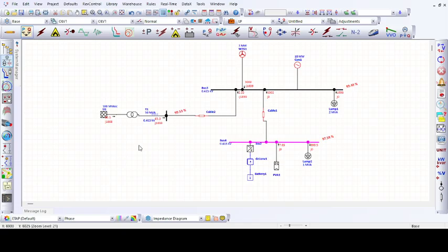Yes, so we can see that the grid source is lightly loaded, and this cable is heavily loaded, and most of the power is taken from the wind turbine generator and the generator. It has 99.48 percentage of voltage, and 97.5 percentage of voltage in these buses. So this is a small AC microgrid system.